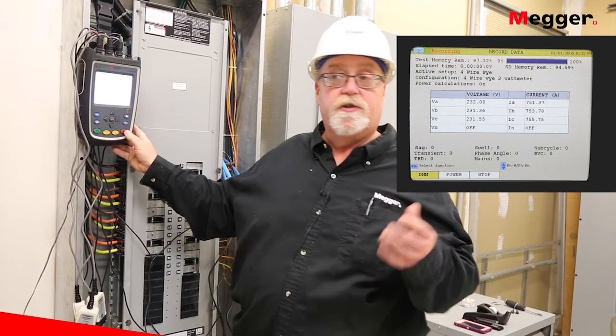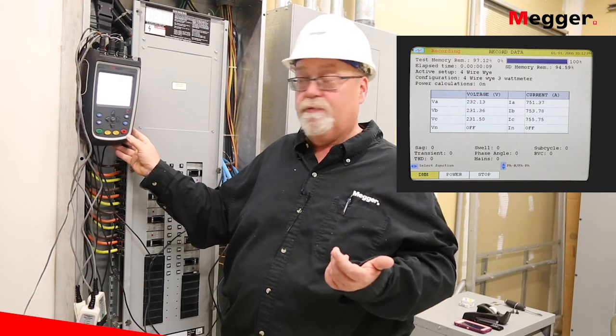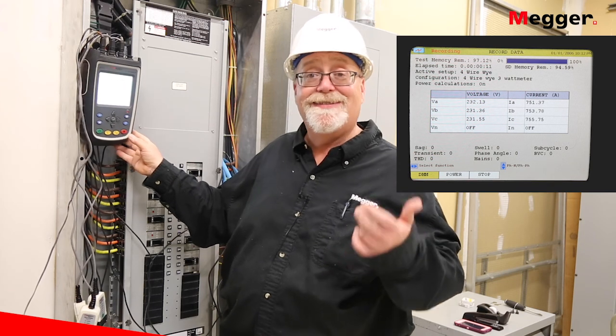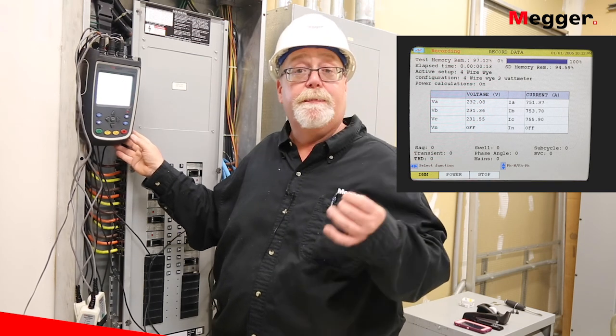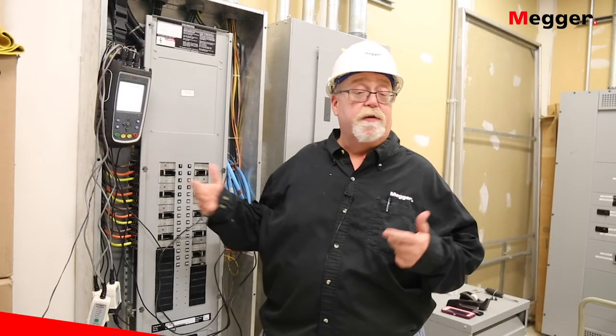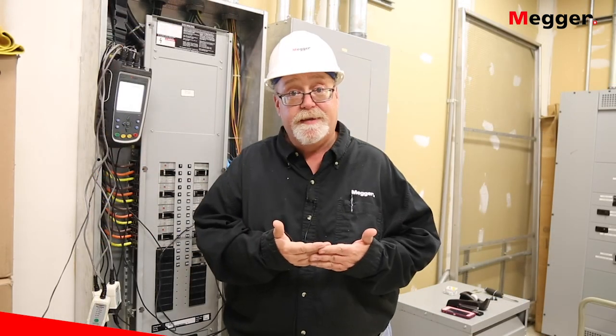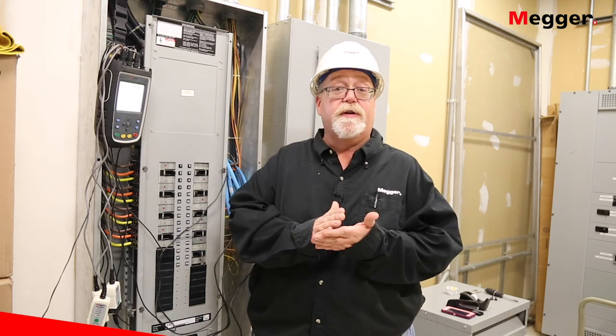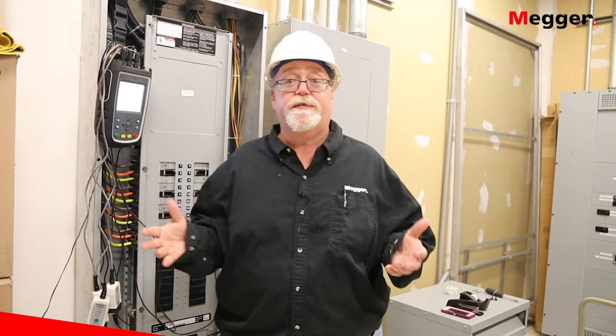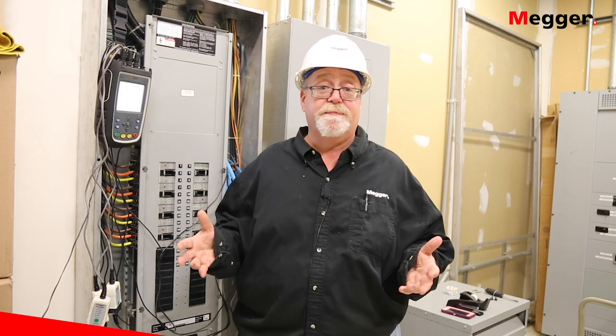The unit is smart enough to know if it's connected properly, and it will let you know if there's any problems and how to correct it. Now that the unit is recording, it's going to be recording cycle-by-cycle data. It's also going to be capturing waveforms up to 10 seconds on every time the motor starts up.